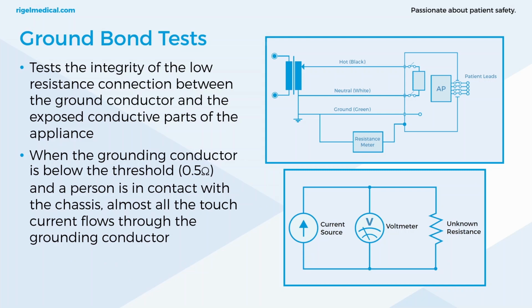Okay, so we know that Class 1 equipment has a ground conductor that prevents harm to anyone. It's a proven safety measure for preventing electrical shock. So below the threshold of 500 milliohms in NFPA 99, and that is the threshold for failure. Any value measured below this is a pass. But if you think about it like this, if the body resistance is about 1,000 ohms, I think 1 to 2 kilo ohms, even at the maximum allowable value of 0.5 ohms, that's still 2,000 times less leakage current that would flow to the human body, and it would go to the ground instead. We also measure that leakage current with the preceding tests.